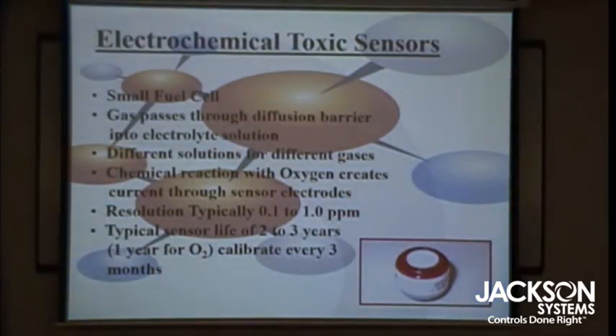An electrochemical sensor is like your car battery. You have a couple of electrodes in there. You have current across the electrodes that gives you the proportion of the gas. So when you do a CO sensor, for example, you choose an electrolyte. An electrolyte is the conductive fluid. The electrolyte reacts with the gas that you're looking at, and you get a current. And that change is proportional to the gas. If you have very high concentrations for long periods, you wear out the cell because you use all the electrolyte, like your battery.